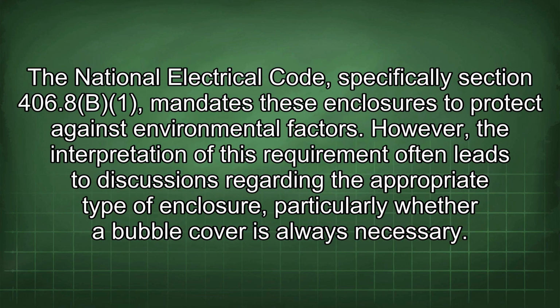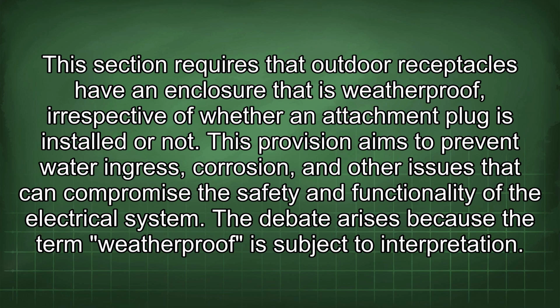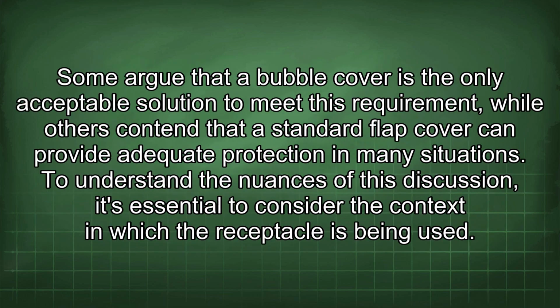The National Electrical Code, specifically Section 406.8(B)(1), mandates these enclosures to protect against environmental factors. However, the interpretation of this requirement often leads to discussions regarding the appropriate type of enclosure, particularly whether a bubble cover is always necessary. This section requires that outdoor receptacles have an enclosure that is weatherproof, irrespective of whether an attachment plug is installed or not. This provision aims to prevent water ingress, corrosion, and other issues that can compromise the safety and functionality of the electrical system. The debate arises because the term weatherproof is subject to interpretation. Some argue that a bubble cover is the only acceptable solution to meet this requirement, while others contend that a standard flap cover can provide adequate protection in many situations.